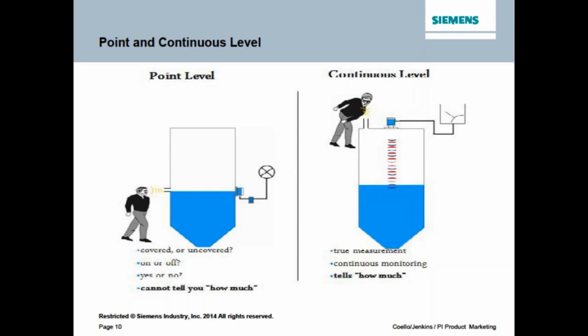There are two different types of level measurement: point level and continuous level. The majority of our presentation today focuses on continuous level. The main difference is that with point level, we simply tell you if the level inside a vessel is above or below a certain point. In this example, we have a point level switch installed horizontally into the vessel -- if level is below that point we have one state, and if level goes above it we change states. So it simply tells you level is above or below that point. Continuous level, on the other hand, tells you exactly how much is inside your tank at any given time, and we typically correspond that to an analog 4 to 20 output.